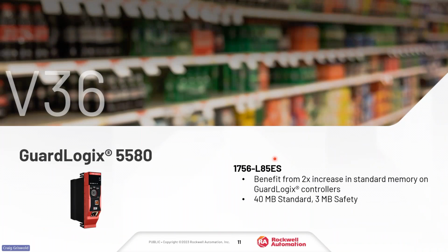So we released a new GuardLogix controller, and the big difference is it has an increase of 20 megabytes of standard memory for GuardLogix and 3 megabytes of safety. The previous version, the L84ES, offers 20 megabytes and 6 megabytes of safety. So customers that need additional space, a little less space for safety but additional space for standard, that's where the L85ES will come into play.